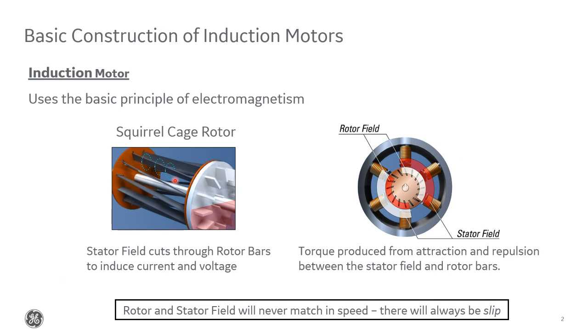So when we energize the stator, the electromagnetic field that it produces essentially cuts through these rotor bars, which induces a current, which effectively magnetizes the rotor. Magnetically, you end up with something like this, where the stator has a north and a south pole, and the rotor has an induced opposite north and south pole, and the force of attraction and repulsion between them, which again is continuously changing rotationally, causes a torque that spins the rotor and drives the load. Now here we're showing these poles exactly locked in, but in reality, the rotor is following the stator's lead and there's going to be some inherent inertia. So the rotor will always lag a little bit behind the stator field. This lag in speed is what we call the slip. So an induction motor will always have some value of slip.